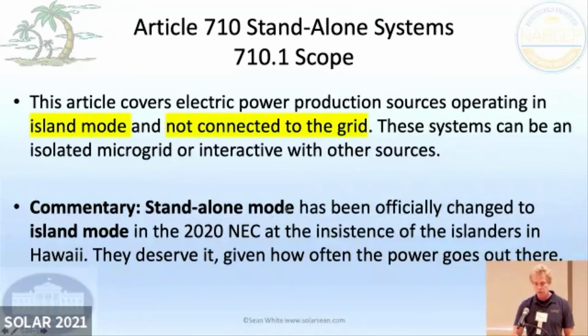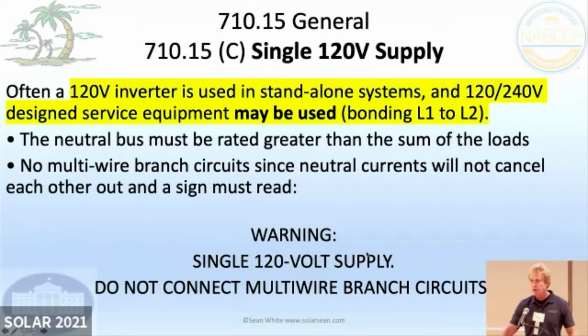710. Some of the things that they've done a little bit differently: they're starting to transition from the word standalone to island. So they call it standalone mode, they call it island mode. So it's an island of electricity. And so that sounds good. I did a class for all the inspectors in Hawaii a few months ago, and that's why I left the palm trees up here, and we call it island mode, and it makes them happy. If it's grid tied, we call it anti-islanding. So anti-islanding means it can't become an island of power. So if the grid goes down, of course, you can't power the whole neighborhood, so it shuts off.